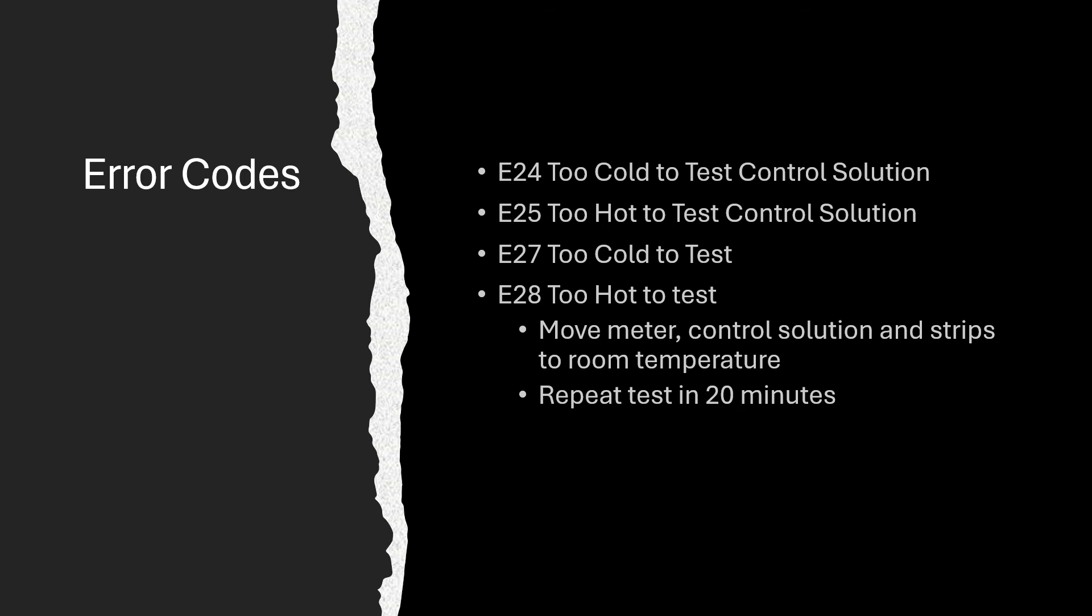E28, too hot to test. For all of these codes, you'd want to move the meter, control solution if you're doing a control solution test, and test strips to the appropriate temperature, wait 20 minutes and repeat the test.